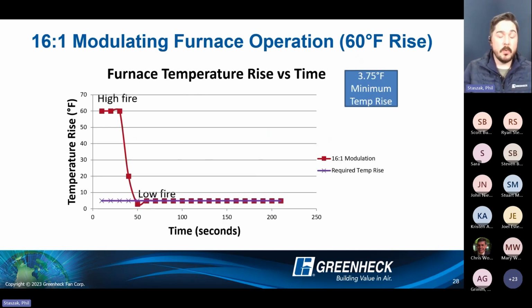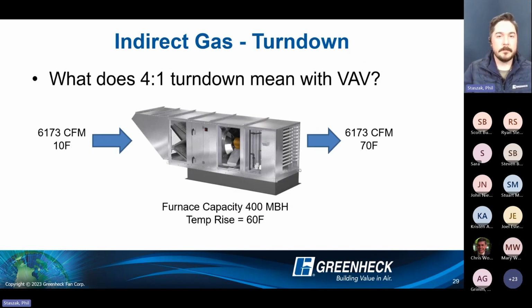So 16-to-1, this is what that looks like. Furnace fires on in high fire. Your minimum temp rise now, if you do the math, is 60 divided by 16, 3.75. If you only need a 5 degree rise, it can just sit there in low fire and maintain all day long. And remember, 25-to-1 is built into direct gas fired equipment.